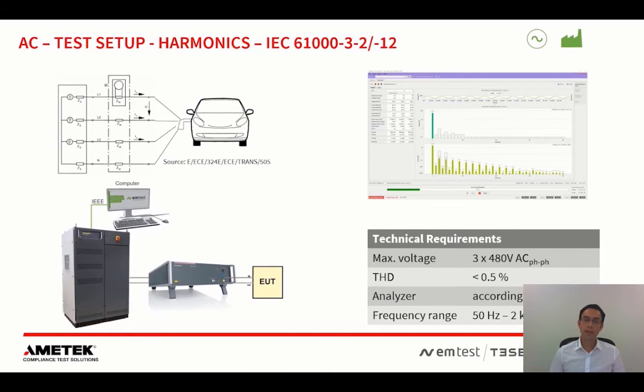Typically the voltages that are required are three-phase 480 volt or maybe sometimes 690 volt line to line. The source needs to be very clean, as I said, so it needs to have a total harmonic distortion below 0.5%. And what is important, you cannot just use any power analyzer, but you need a power analyzer according to IEC 61000-4-7. That's an IEC document that specifies exactly how the power analyzer needs to measure those harmonic currents. The frequency range is the normal IEC 61000-3-2 and -12 frequency range. So it goes from the mains frequency 50 Hz up to the maximum, the 40th harmonic, which is 2 kHz.